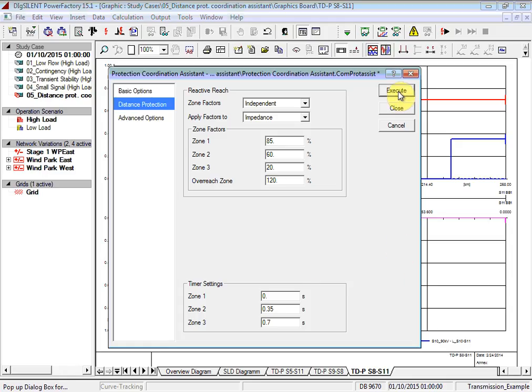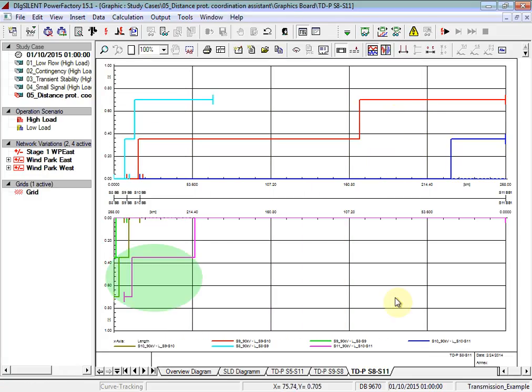Select the Execute button. Here we can see the zone reach settings have changed. In this case, zone 2 and zone 3 now reach beyond the end of the long line. You can see that zone 2 and zone 3 are also providing some degree of backup protection for the lines between substation 10 and substation 9 and substation 9 and substation 8. In this case, you can see that there's definitely an improvement with regards to the settings. Now that we're happy with the settings that have been calculated, let's write these settings back to the installed protection devices.